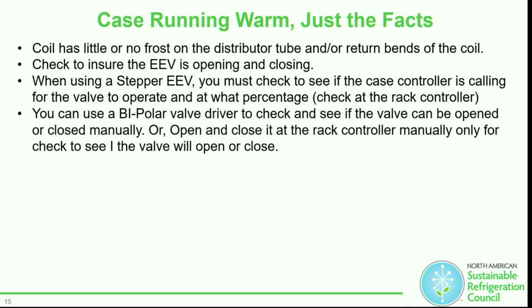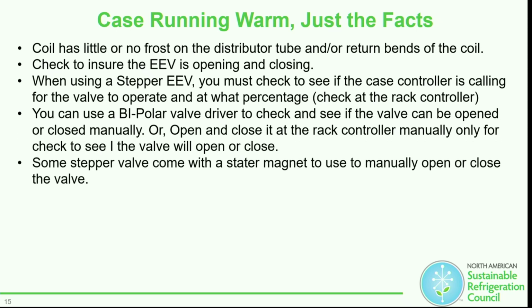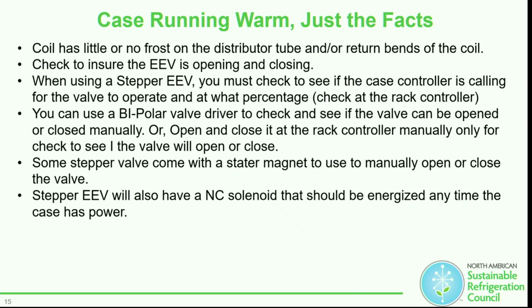You can use a bipolar valve driver to check and see if the valve can be opened or closed manually, or open and close it at the rack controller manually to check to see if the valve will open and close. That also might be another reason why a valve is not fully seating and why you might have an iced up coil. A lot of these valves have an overclose percentage, and I'll go through that in a minute, but just remember that for right now. Some stepper valves also come with a stator magnet to use to open up manually. Carel is one of these manufacturers. A lot of ones do not. The stator and stem is all in one, like on the Sporlan and Danfoss expansion valves.